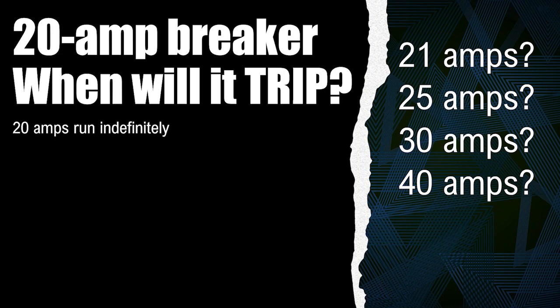So with that being said, if you've done your math correctly and you've done 125% of your continuous loads and 100% of your non-continuous loads, you can load this breaker right up to 20 amps and it's designed to run indefinitely.